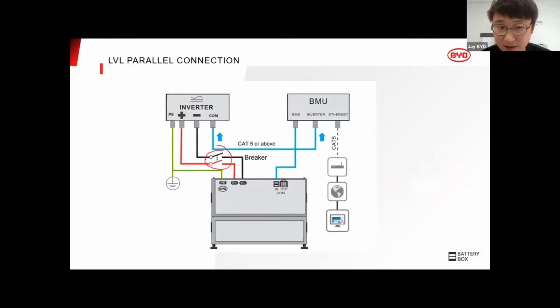So what I mean is, as simple as you have the 15.4 battery here, in Australia you need an external circuit breaker. Even though our batteries have a power switch and also an internal fuse, with the new standards you will need a circuit breaker to shut down the entire system with one click or one switch. Doesn't matter if it's a BYD battery or other batteries that say they have internal circuit breakers, it doesn't really matter. If you follow the standards and have a larger battery system, you need an external circuit breaker to shut down all the batteries with one switch.